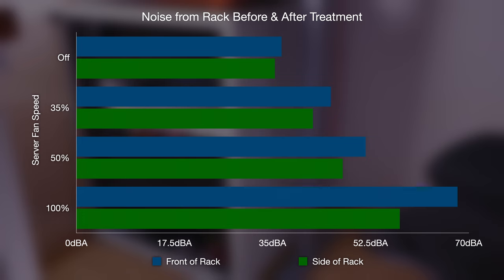And in that server's BIOS, you can set the fans to different speeds. And that server can get very loud at high fan speeds. Thankfully, it doesn't need to run at that speed normally. So what I did is I put that server in the rack both before and after, ran the fan at various speeds, 35%, 50% and 100%, and measured the noise levels. And I measured the noise level from both the front of the rack and the side of the rack. So at the front, I'm measuring the sound through the glass, and at the side, I'm measuring it through the metal that will later be covered with insulation on the inside.